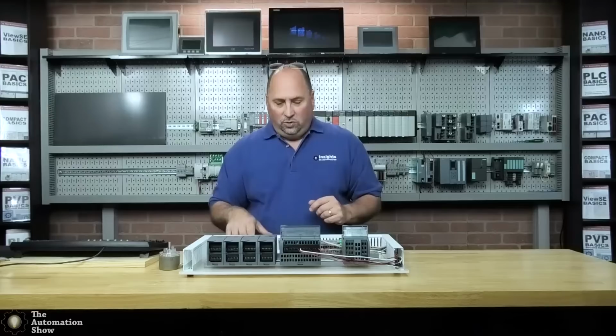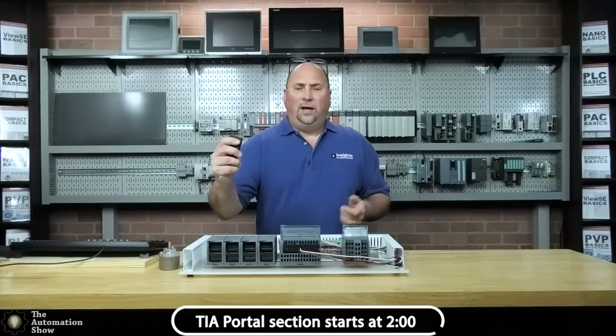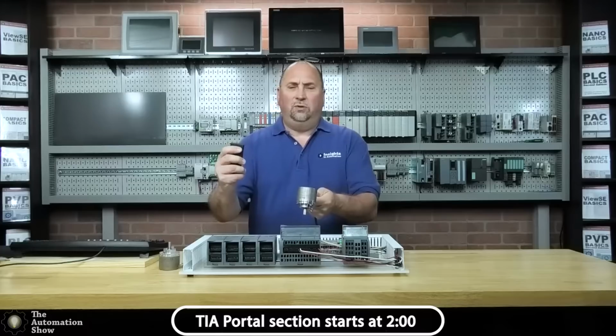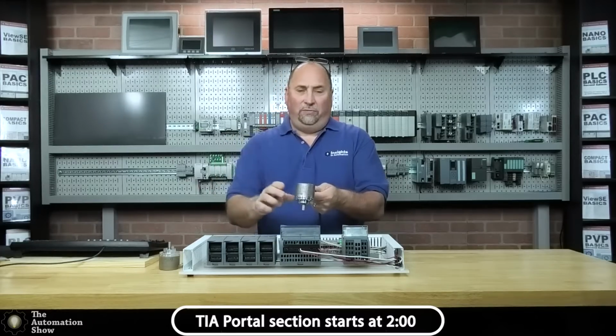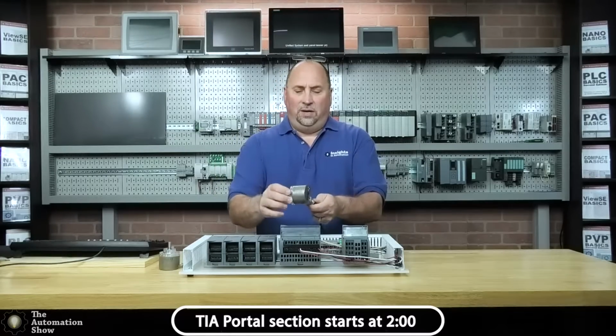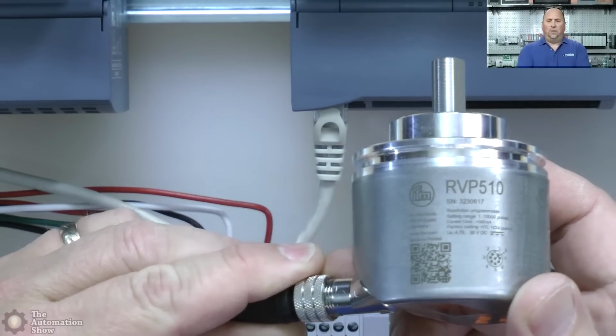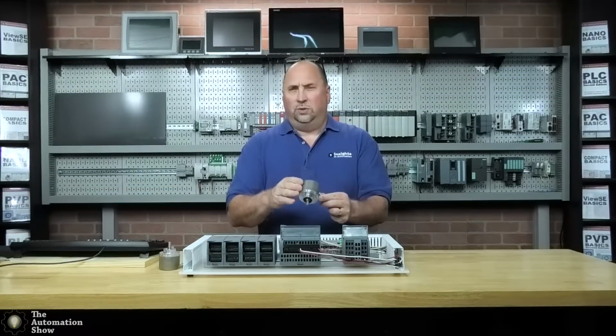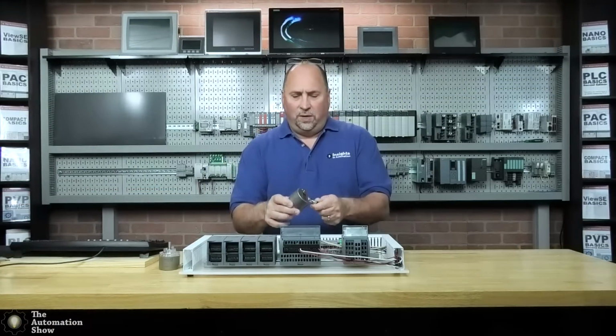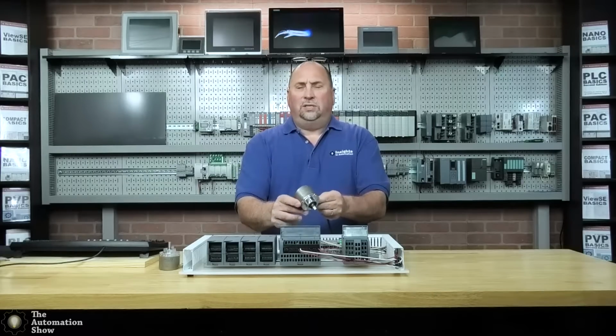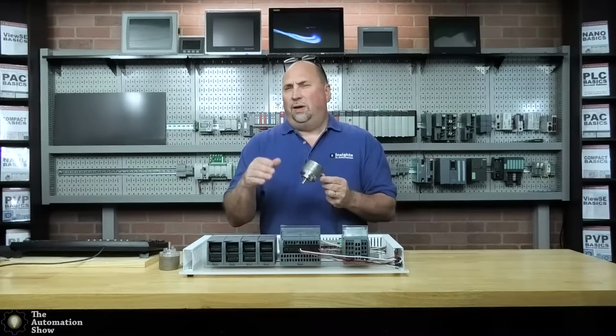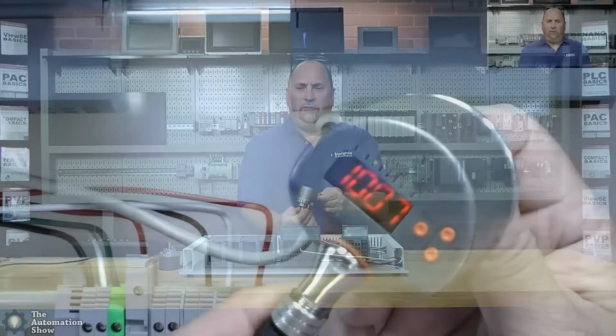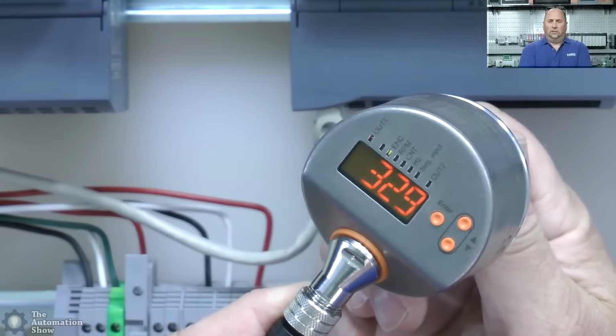And with that, let's go ahead and take a look at the encoder itself, and we'll talk about the wiring. I know I've used this encoder in a number of videos, so you may already be familiar with it, so I won't spend too much time on it. But this is the RVP510 from IFM. It's also an IO-Link encoder, so we'll actually use it with IO-Link in the future. But this unit is set up out of the box with 1,024 pulses per rev, and you can see I can turn it here, and it's going.